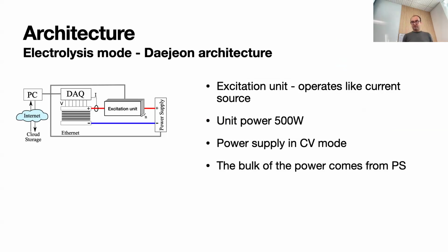So, electrolysis mode. This is a typical architecture that we are using, and this is the thing that we actually installed here in Daejeon. In this case, the stack is a power consumer in the circuit. It's not a power source. So I'm going to put it as a load.